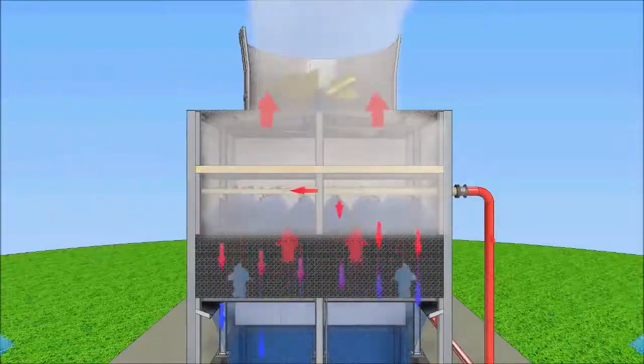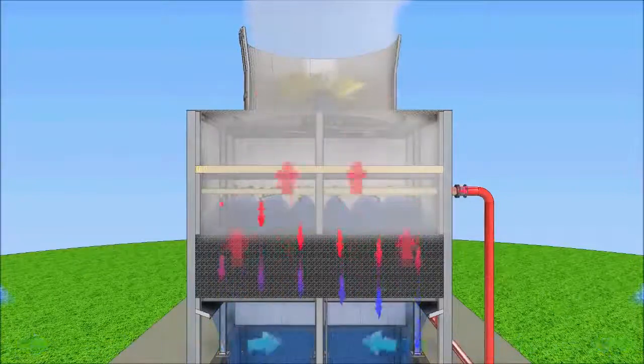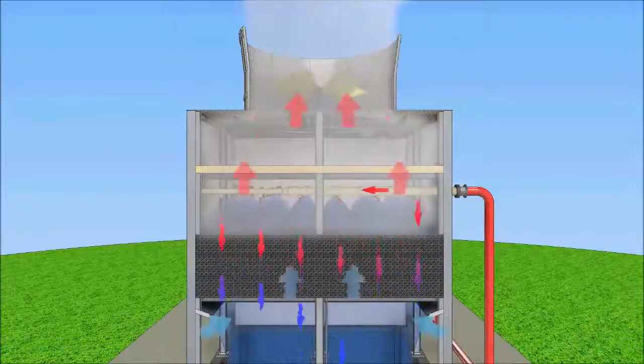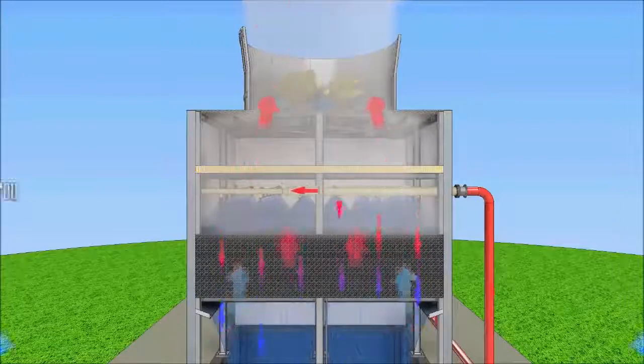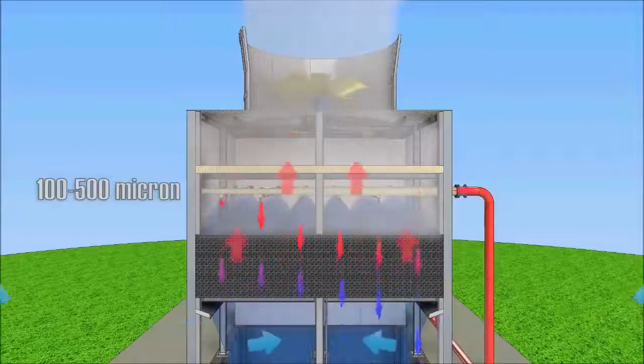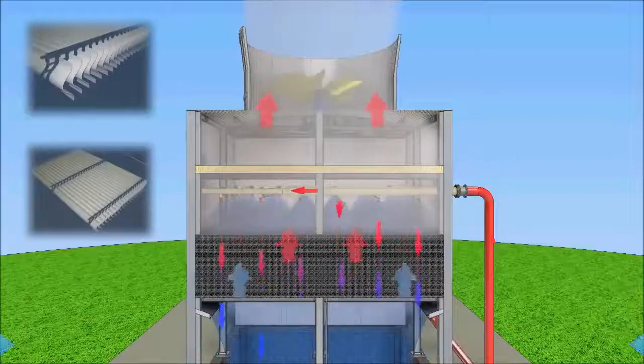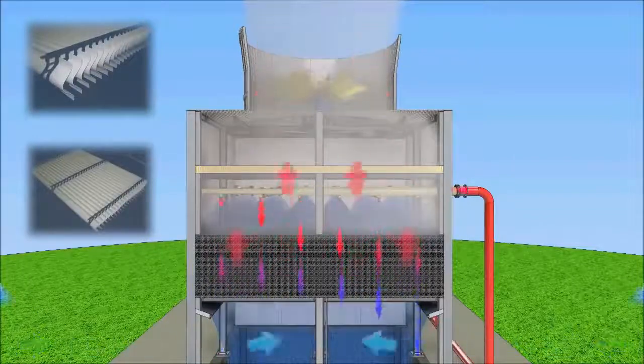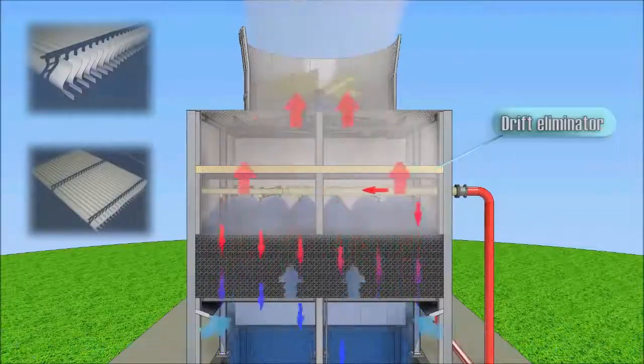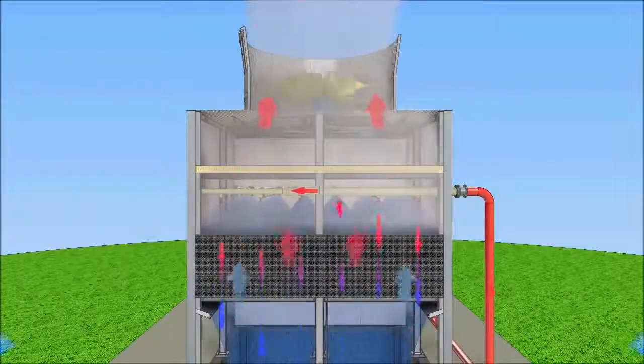When operating a cooling tower, air is saturated with water vapor and contains water droplets with sizes of 100-500 microns. To prevent entrainment of water droplets, a drift eliminator is installed above the water distribution system.